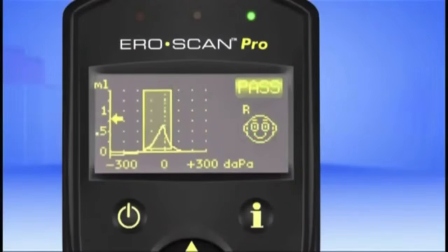This is an example of the tympanometry test results screen. On the left, you can see a graph of the tympanogram. The curve that appears on the graph represents the movement of the eardrum during the test. The area surrounded by the box is valid for normal tympanograms. When the peak of the curve appears inside the box, the screening is generally considered a pass.